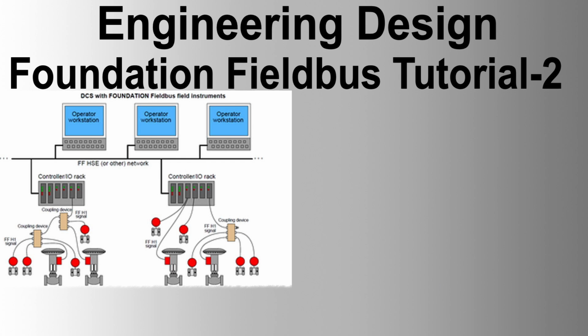Scaling parameters. Some function blocks need scaling of the data as 0 to 100%. A scaling parameter is a record of 4 components: EU at 100%, EU at 0%, unit code, and point position.